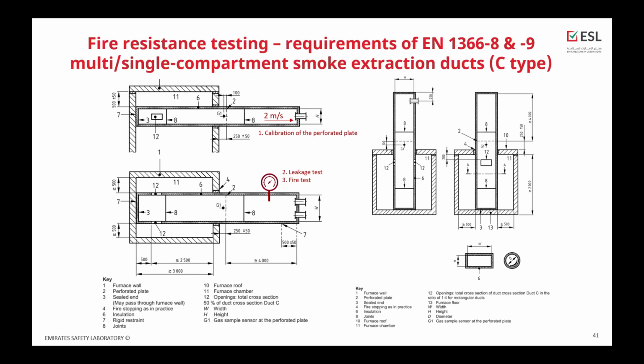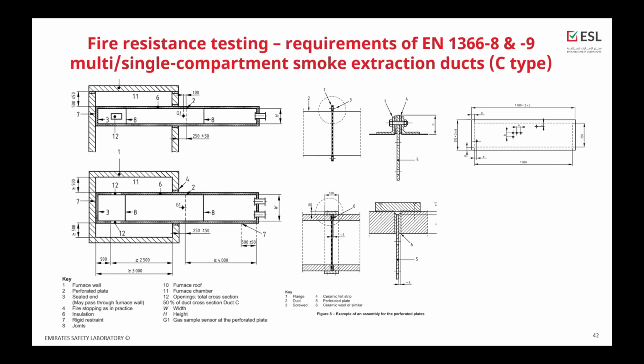And as you can see, the construction of duct C is quite similar to duct B. So you can start wondering how we can assess the leakage of this duct C when we have an opening in the furnace or within the construction of the duct. Basically, we are assessing the leakage based on the oxygen measurement, which is done before the perforated plate, this is G1, and within the flow measuring station. Based on these measurements, we are doing the calculations to assess the leakage of the duct system.